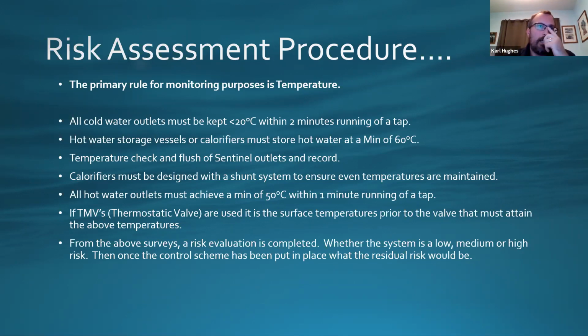So what you're looking at is your hot water provided to the TMV of greater than 50 degrees and your cold water being less than 20 degrees. You'd usually be able to get the cold water from the cold water tap. From the hot, you would take it from the actual pipework feeding it. Obviously, if you're going to go into scald risk, you need to look into whether the TMV is set right or not. One of the recommendations, which you'll see afterwards, is that these need to be serviced. So based on the information you'll get from the cold water storage tank, from how the hot water is, from whether there's dead legs, etc.